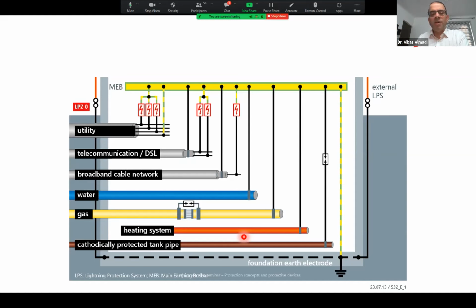There is no possibility of arc. There is no possibility of any fault current flowing from the equipment. Equipment is protected, services are protected. That is the basic principle. Equal potential bonding. Equipotential bonding. Everything at the same potential. In order to do that, bond it together. Bonding cannot be done by live wire sometimes because of the different voltages there, like line, neutral, and earth. So we have to connect them via the SPDs, which act like switches. Simple.